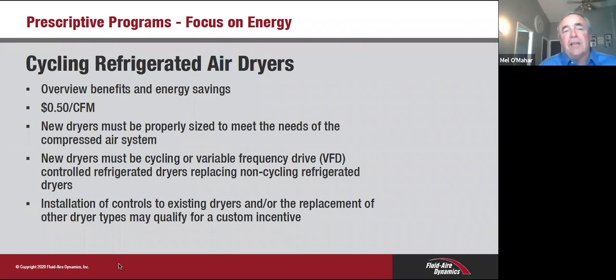One other thing on cycling versus non-cycling. In the non-cycling, that refrigerant compressor is drawing pretty much its full kW the whole time it's running. It's just bypassing gas. So you have zero energy savings if you're using very little air or if you're running at full speed. Also, a cycling dryer or variable speed adds durability and longevity to that compressor. If it's not running at full demand, it's going to be easier on the components inside. So just like with compressors, with air dryers you're going to pick up some dependability and longevity as equipment goes.